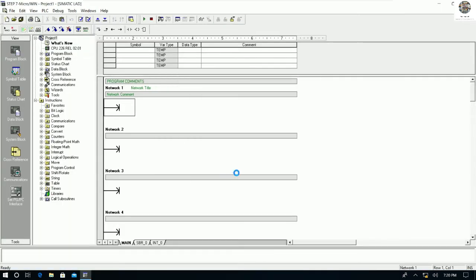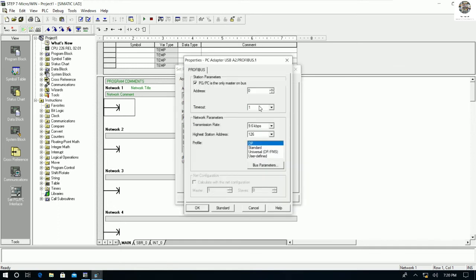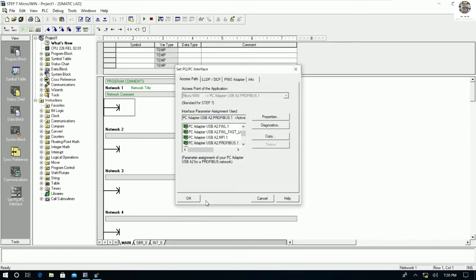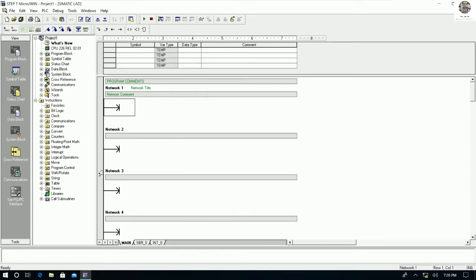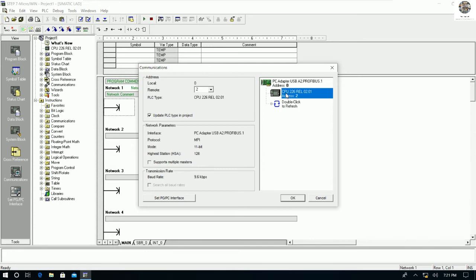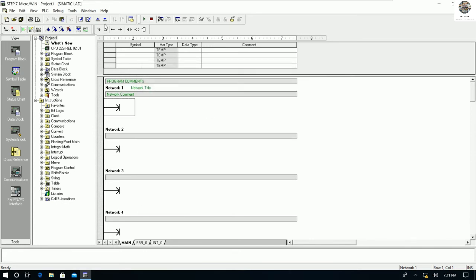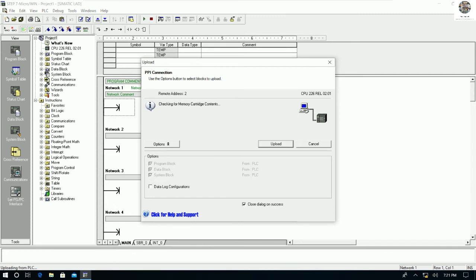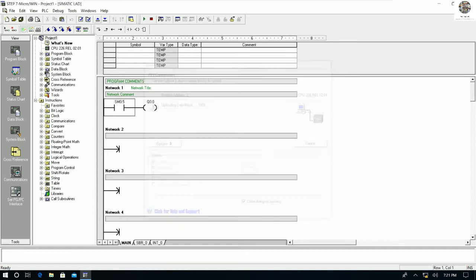Go back to Set PG/PC Interface again — don't forget to check this. The checkbox should be checked, and the baud rate should be set to the lowest value, which is 9.6 kbps. Press OK, then go to Communication and double-click to verify. The checkbox is already checked. Now we can upload using this setting.